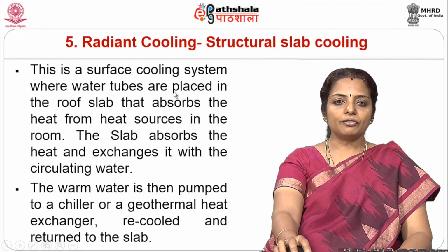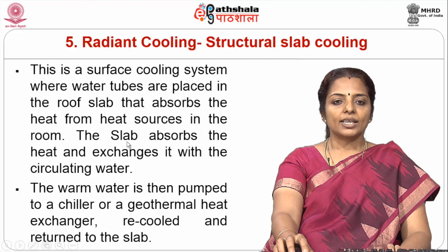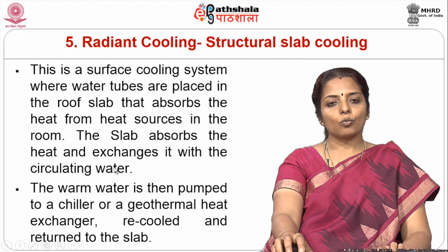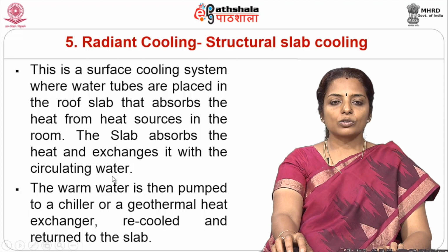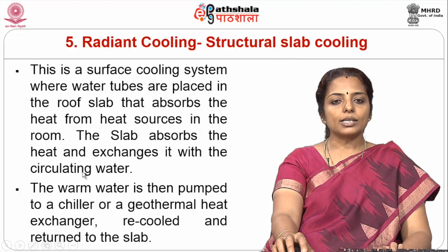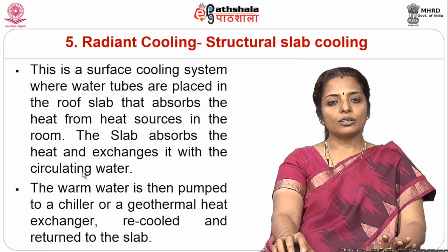This is a surface cooling system where water tubes are placed in the roof slab that absorbs the heat from heat sources in the room. The slab absorbs the heat and exchanges it with the circulating water. Instead of air, we can also use water to pump in, because water has more thermal capacity. The warm water is then pumped to a chiller or a geothermal heat exchanger, recooled and returned to the slab.